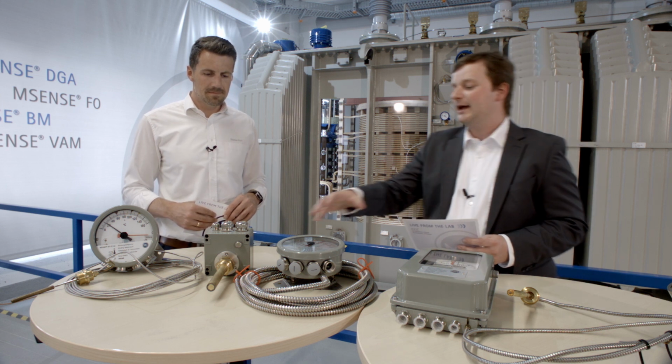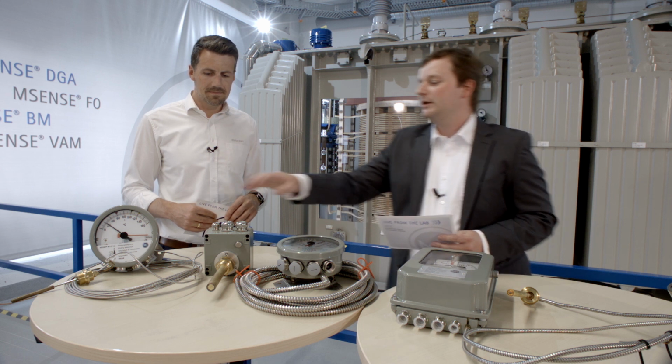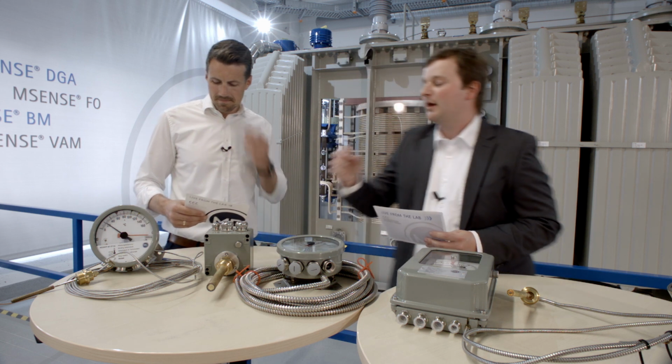This means the entire measuring system, including the probe which is sitting inside the thermometer pocket, measuring the top oil, the entire measuring system is filled with a liquid. And once this liquid is heated up, it is expanding. And with this, there is also the expansion of the Bourdon spring, which is sitting behind the dial. And when the spring is moving because it's heated up, then also the pointer will move up and down and indicate the temperature of the top oil.